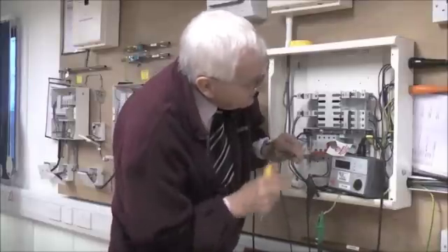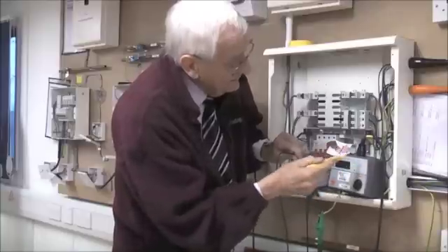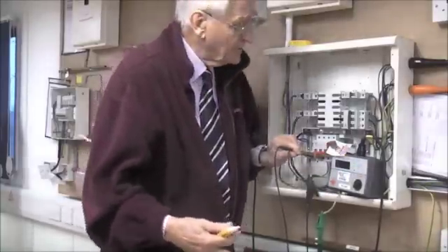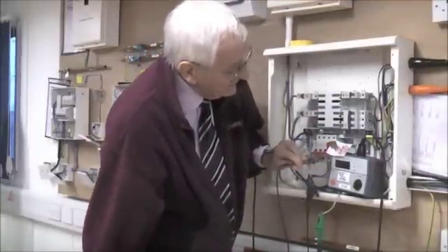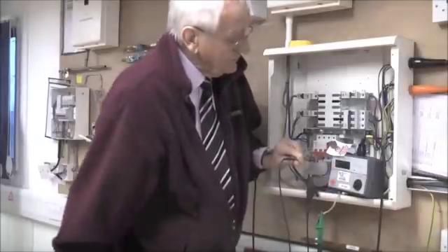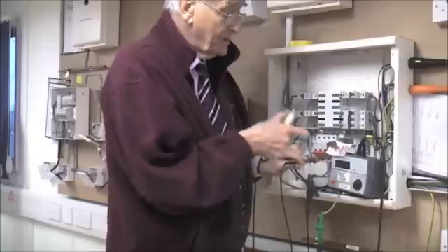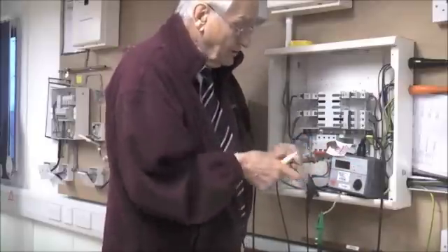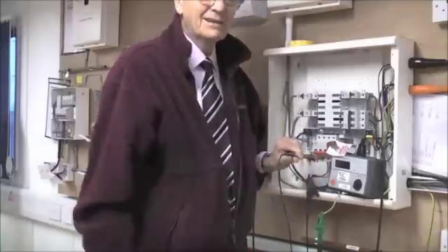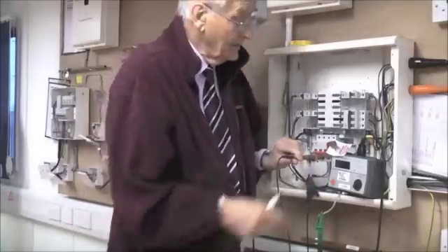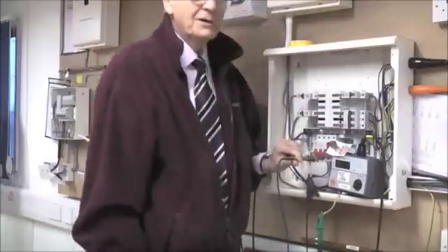I'm on the line. Now it's important to see you've got the correct lights up on your meter to show you haven't got anything crossed over or any volts missing or whatever else. So I've got two green lights here which show I'm correctly connected. I've got a voltage of 236 volts. So I'm about to press this button and put this resistance inside this meter across the line and neutral, sorry across the line and earth conductors. Press the button and we get a reading of 0.49 ohms.